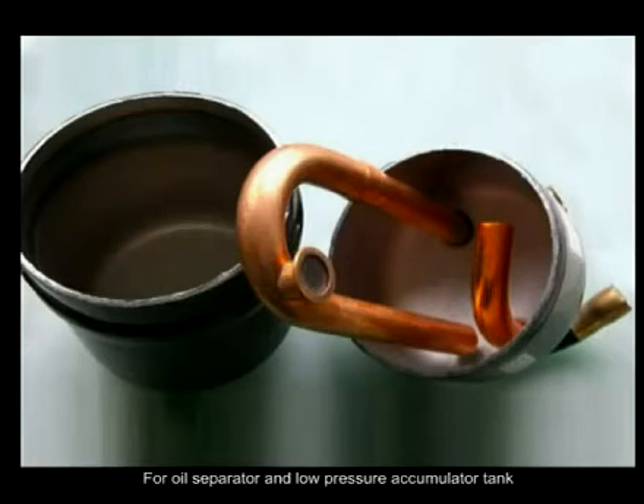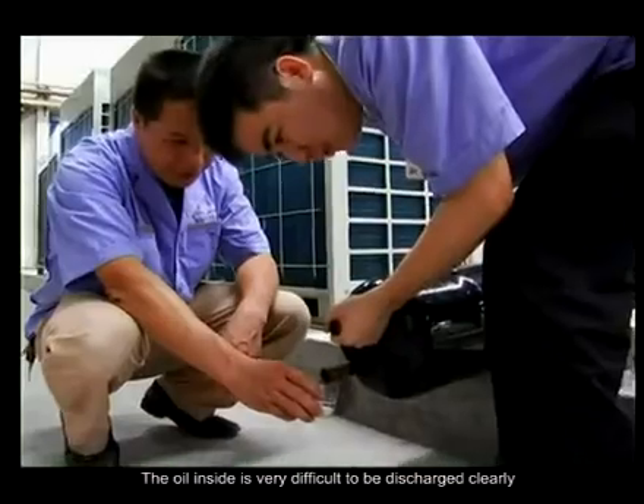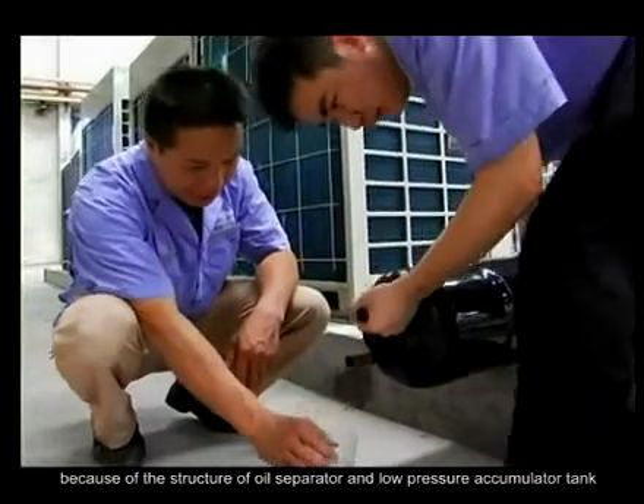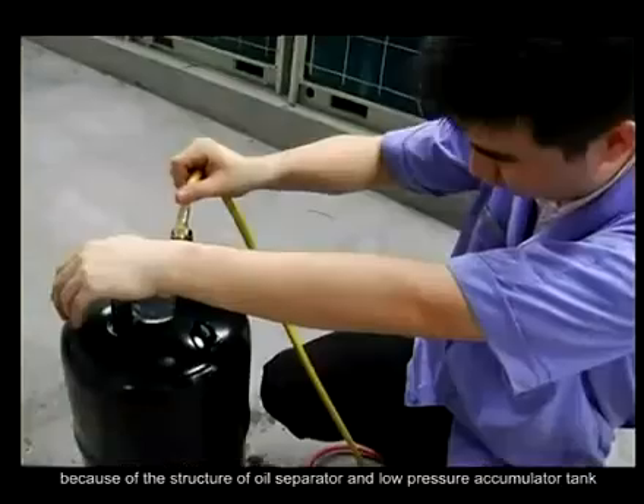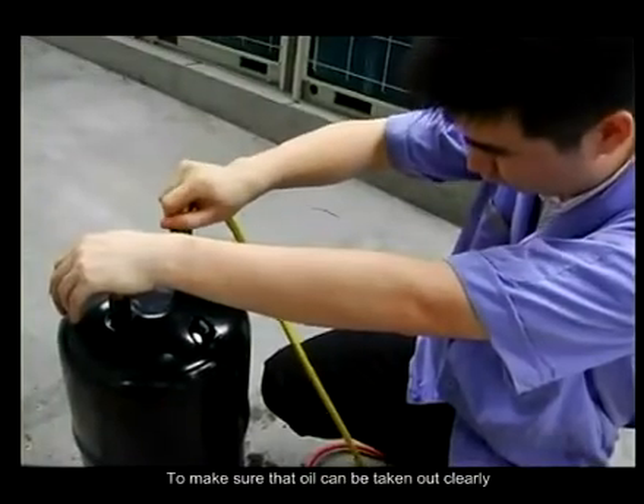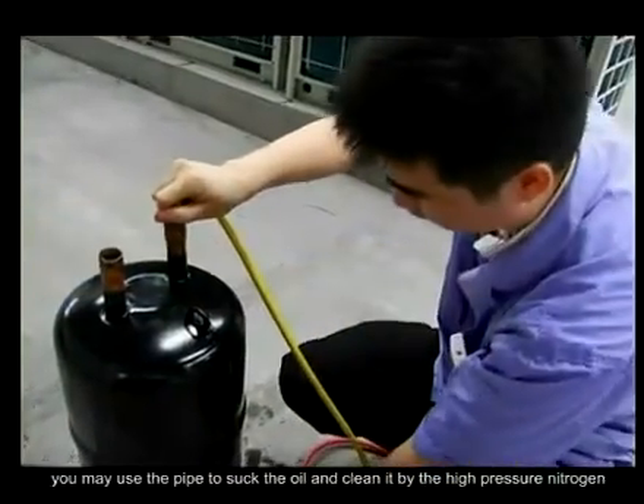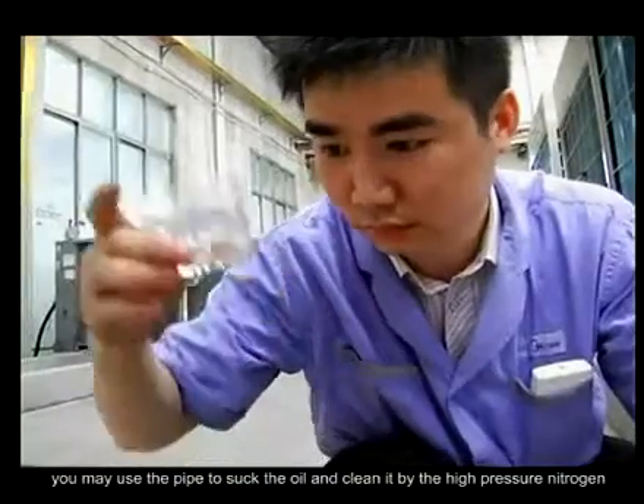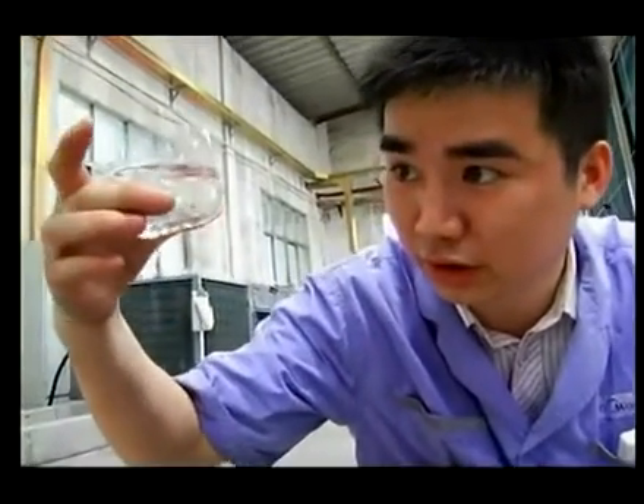For the oil separator and the low pressure accumulator tank, the oil inside is very difficult to discharge completely because of their structure. To make sure the oil is taken out completely, you may use a pipe to suck out the oil and clean it with high pressure nitrogen, or replace it with a new tank.